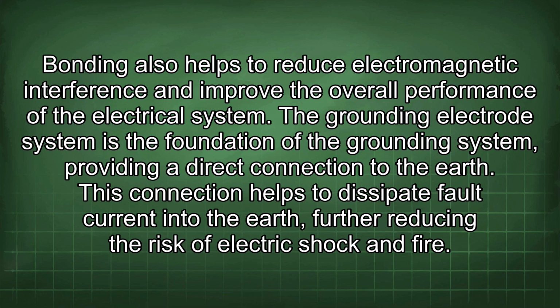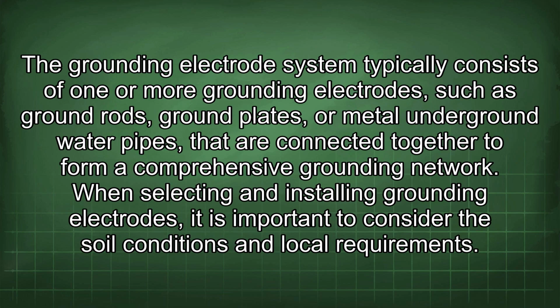The grounding electrode system is the foundation of the grounding system, providing a direct connection to the earth. This connection helps to dissipate fault current into the earth, further reducing the risk of electric shock and fire. The grounding electrode system typically consists of one or more grounding electrodes, such as ground rods, ground plates, or metal underground water pipes, that are connected together to form a comprehensive grounding network.